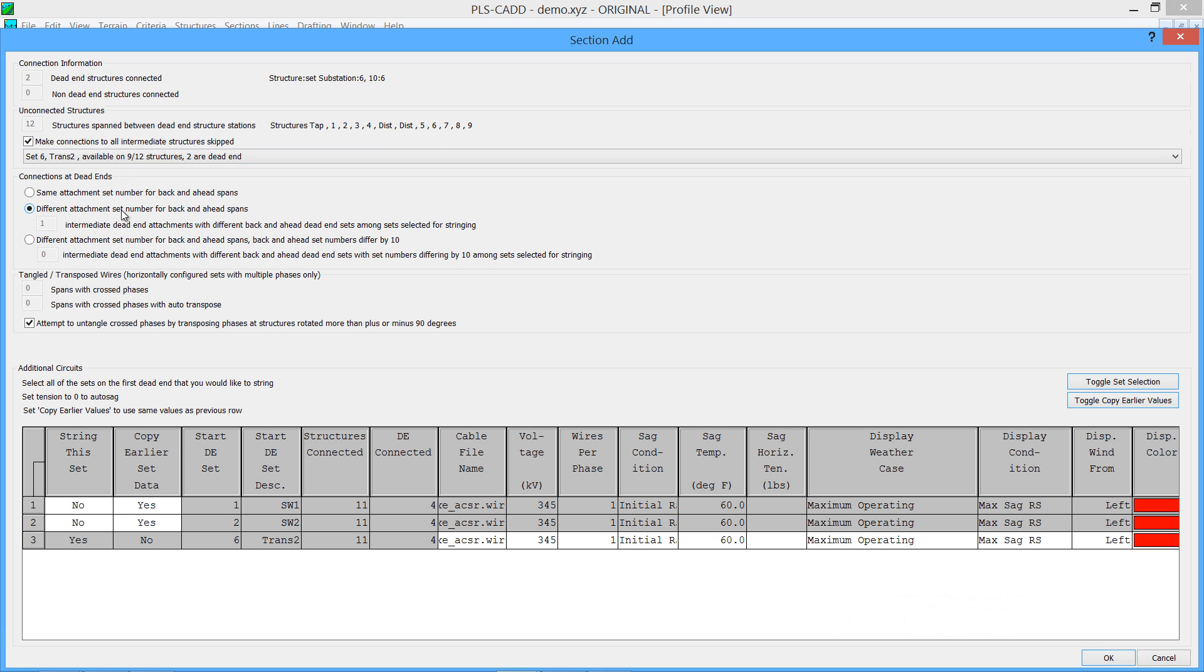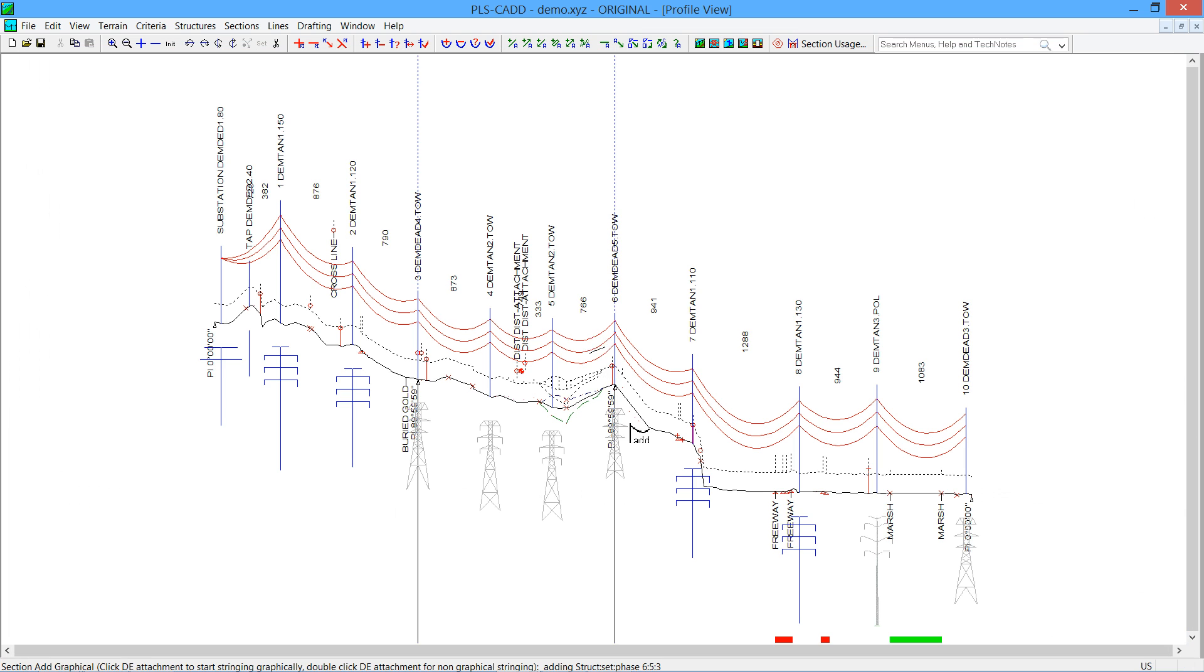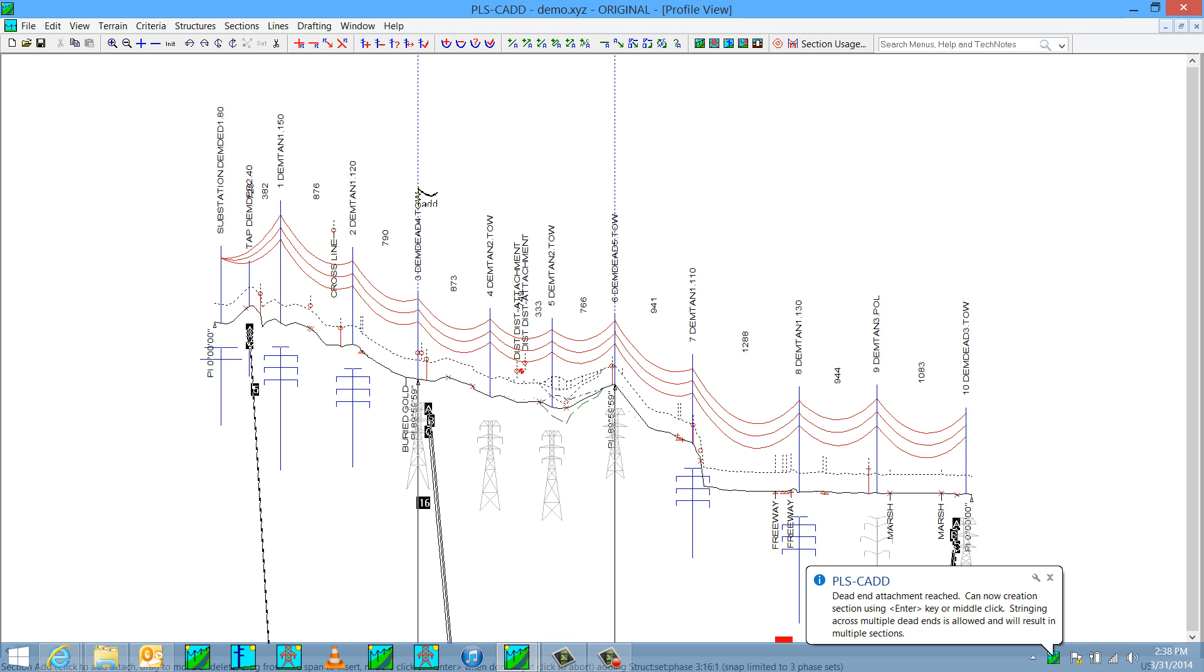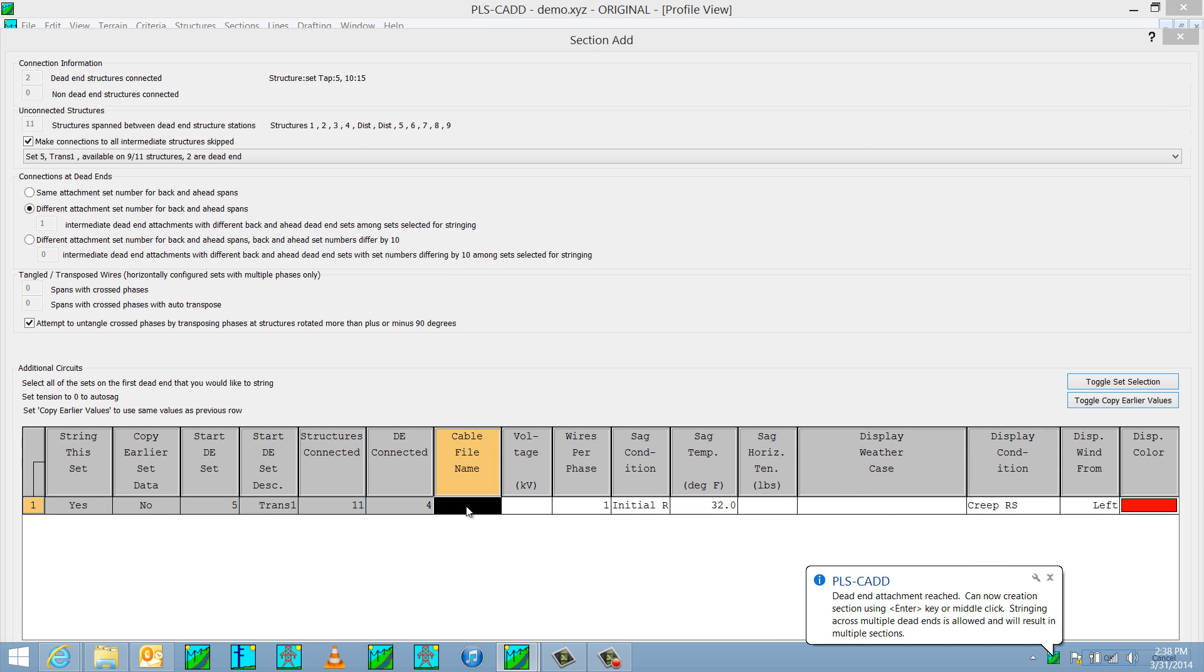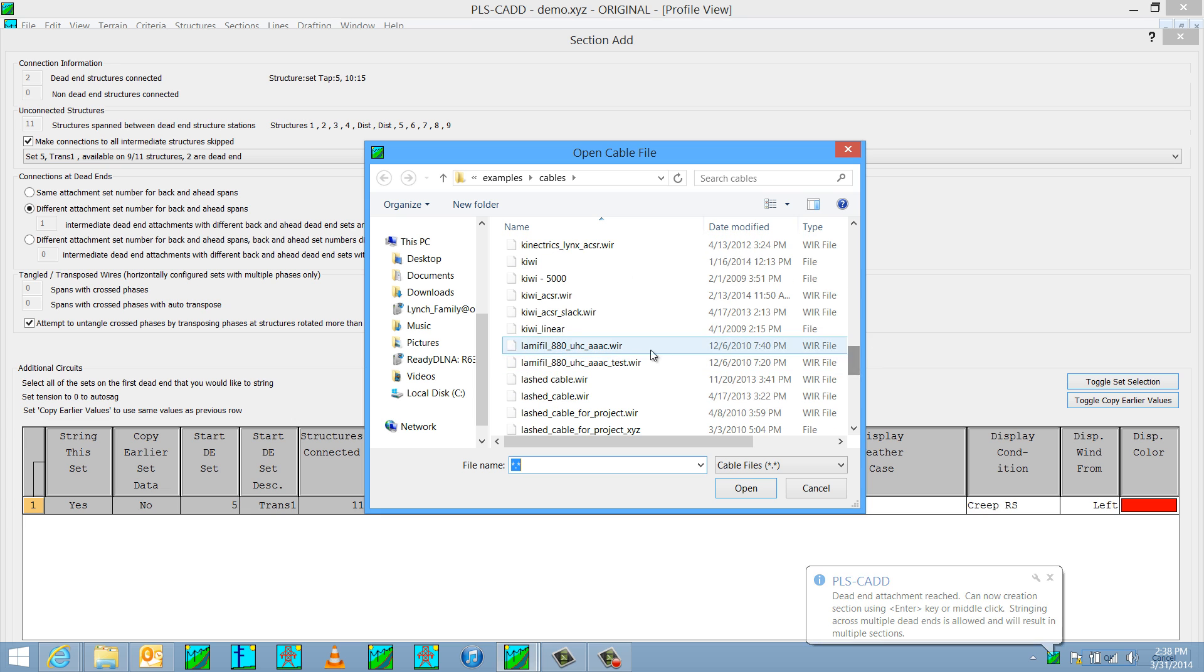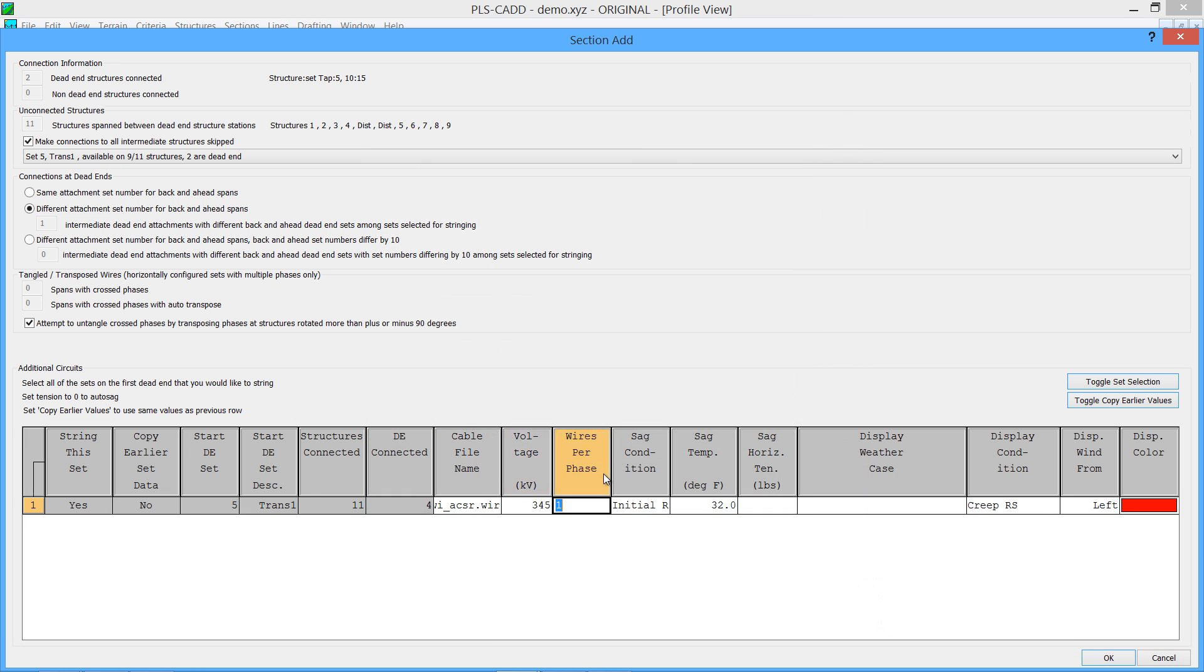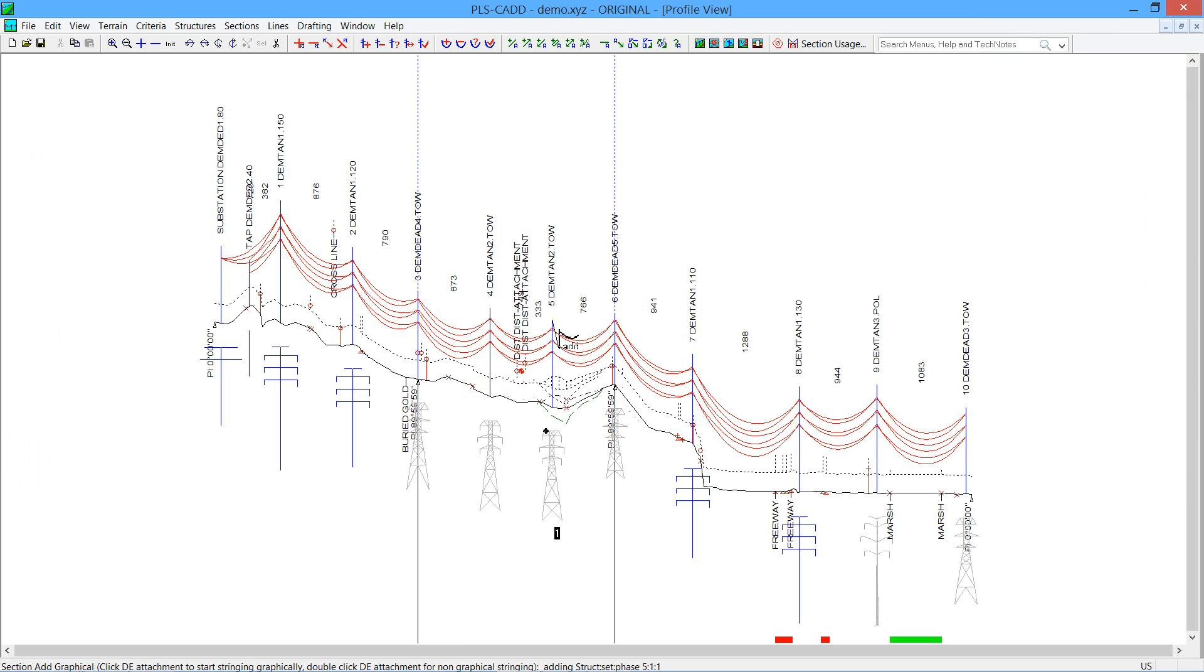And I'm going to say set six here. I'm going to say different attachment set in case you did use set 16 or whatever on the back side. I'm going to click OK. And you will now see all your wires automatically get strung up along the order. So now we could sit here and say, let's go to five, and I'm going to go to set number 15 on the back side of that one. Hit the Enter key. And we'll stay, this one might be, for example, a Kiwi ACSR. And I'll make it a 345 as well. And 60 and 0, and display weather case maximum operating, maximum sag. And that should take care of it. And there we go. So we have our other circuit strung on our line as well.